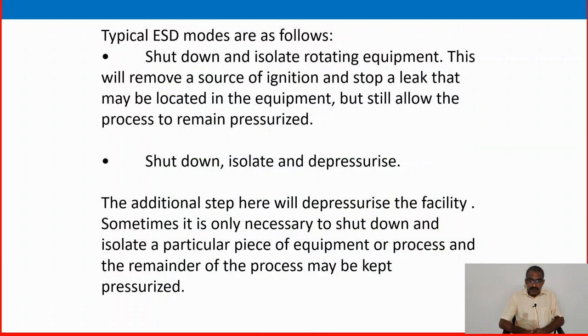Typically, ESD modes are as follows. First, shutdown and isolate rotating equipment — this removes a source of ignition and stops a leak that may be located in the equipment, but still allows the process to remain pressurized. Second, shutdown, isolate, and depressurize — the additional step will depressurize the facility. Sometimes it is only necessary to shut down and isolate a particular piece of equipment or process, and the remainder of the process may be kept pressurized.